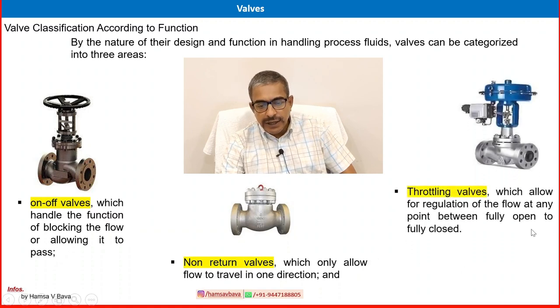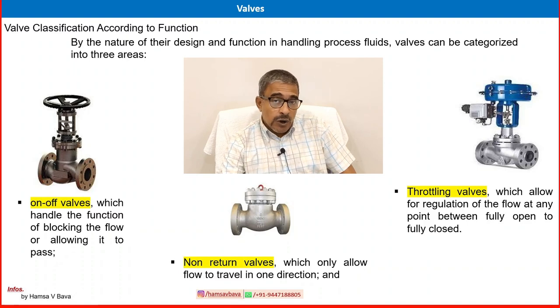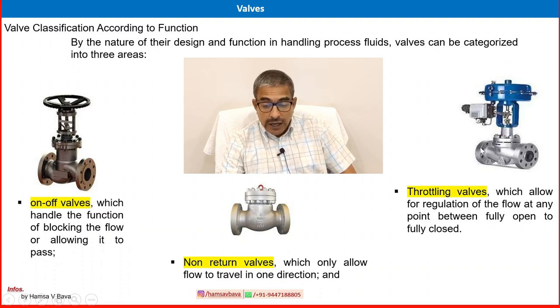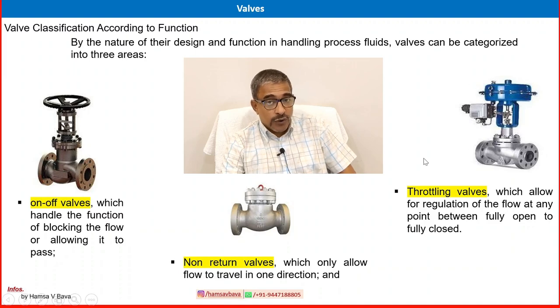The third category is the throttling valve, which is the opposite of an on-off valve. A throttling valve can work as an on-off valve — zero percent or 100 percent open is possible — but mainly it is used for partial positions such as 10, 20, 25, or 50 percent open. Throttling valves allow regulation of flow at any point between fully open and fully closed. It is mainly used as a control valve, but many other applications exist.